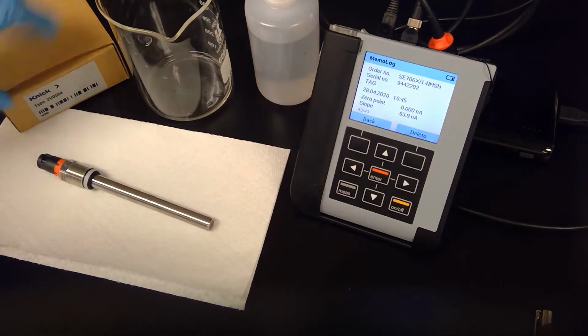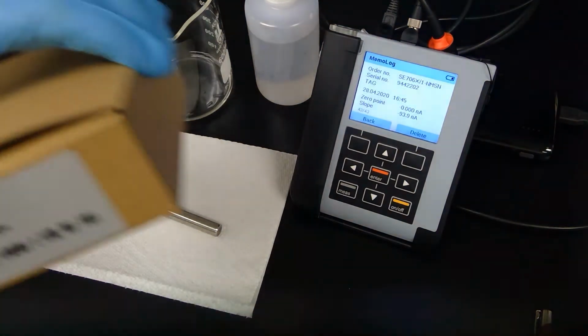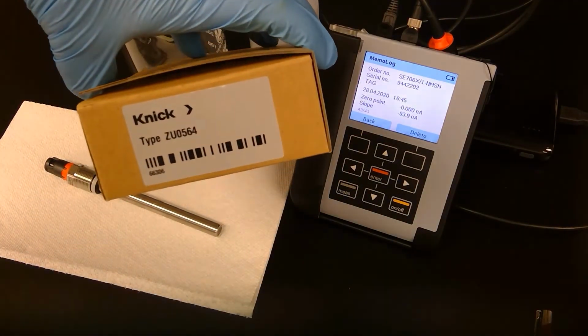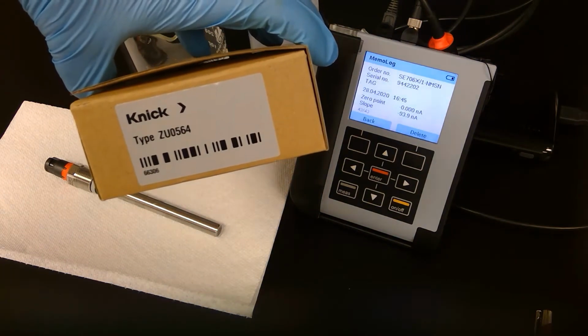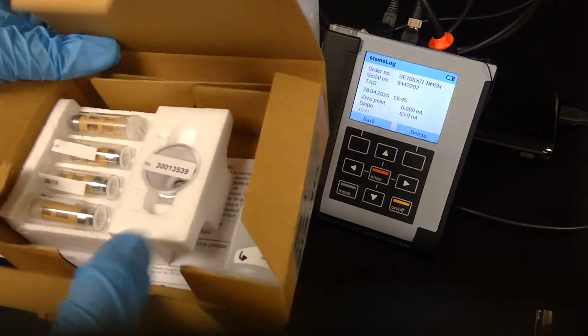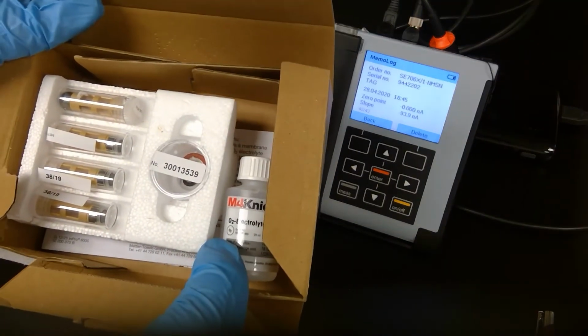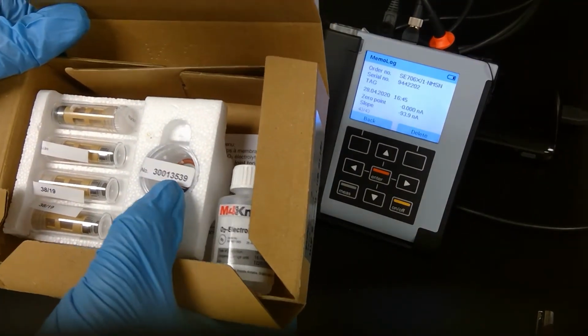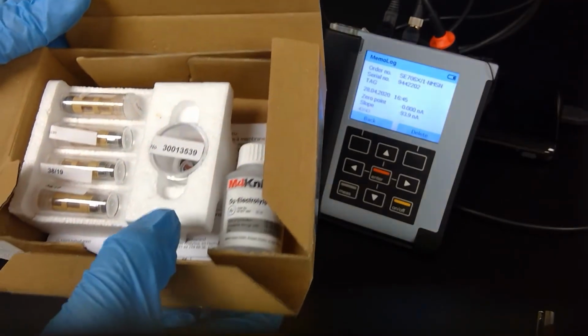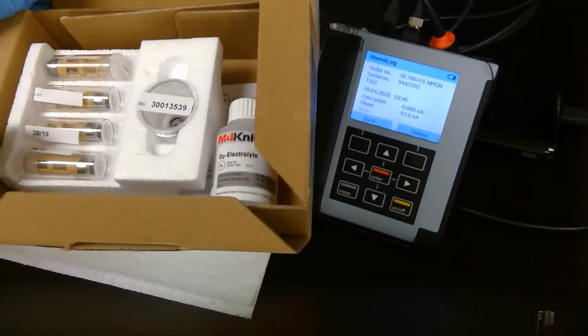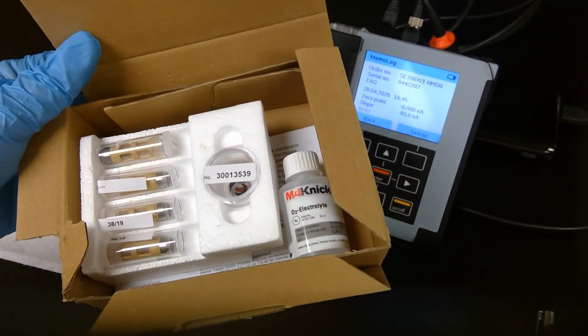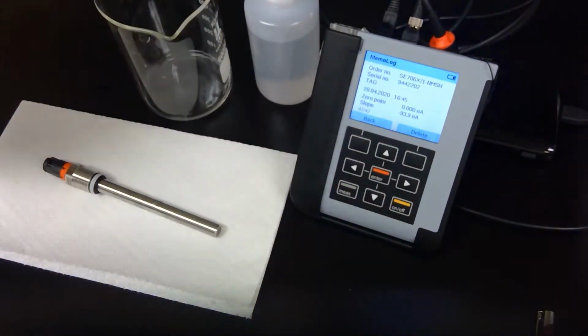What you do need, of course, is a membrane replacement kit. This is what it would be. It's the ZU0564. What you get inside the kit are 4 membranes, an electrolyte bottle, and some spare O-rings, and we'll talk about what those are for. So you can do 4 PMs on a single electrode with this kit.